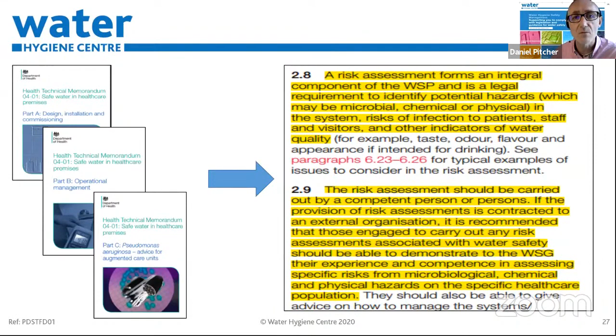Moving on to my third top tip: written schemes of control and water safety plans. Why do we need these schemes of control? If a risk assessment has identified the risk systems you have, great - now you know what you've got. You need a written plan of control for managing, maintaining, fixing, and monitoring these risk systems. The identification of risk systems and associated assets within your buildings is essentially an ingredients list. The water safety plans are, if you like, the recipe or instructions on what you need to do with those risk systems and associated assets.